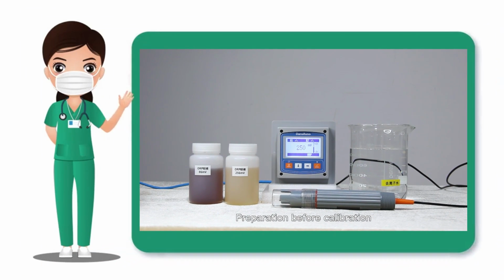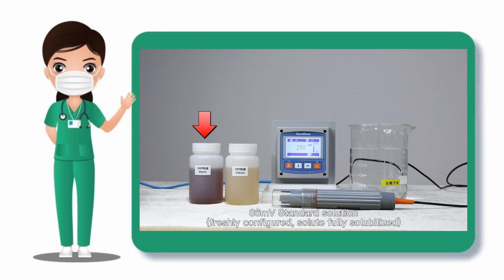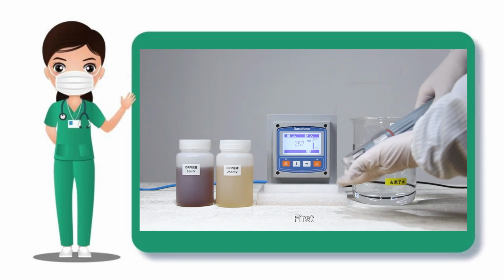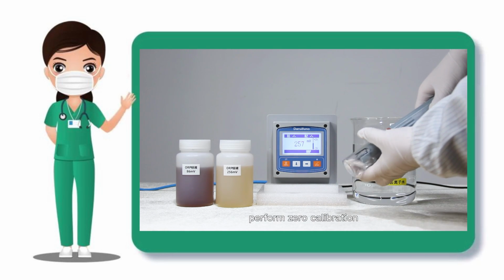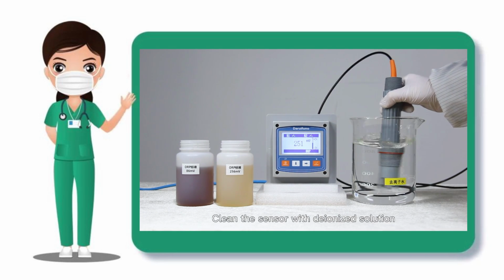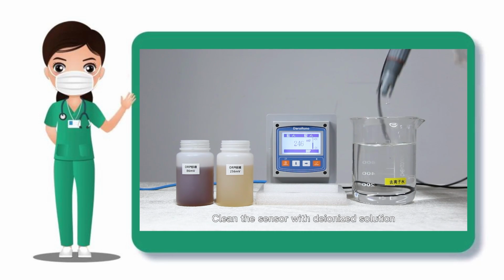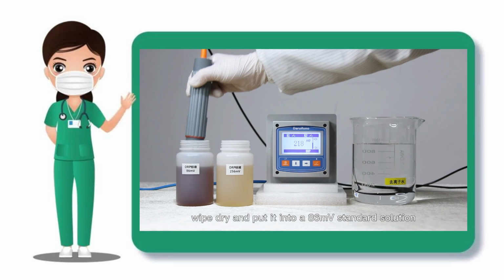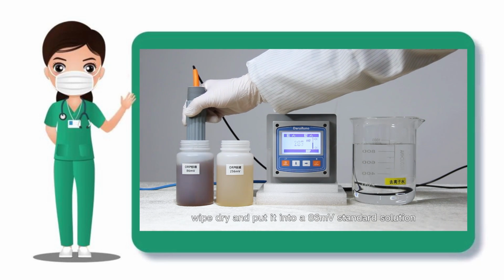Preparation before calibration: 86 mV standard solution, 256 mV standard solution, deionized solution. First, perform zero calibration. Clean the sensor with deionized solution, wipe dry and put it into the 86 mV standard solution.